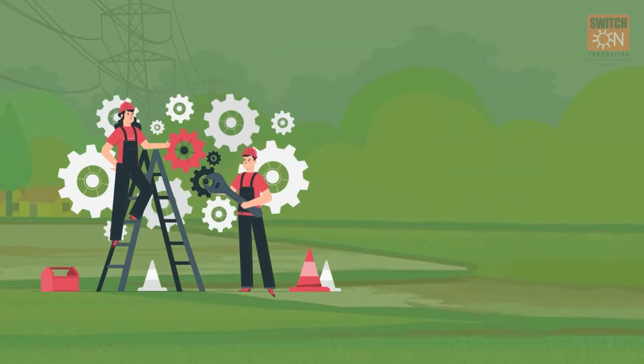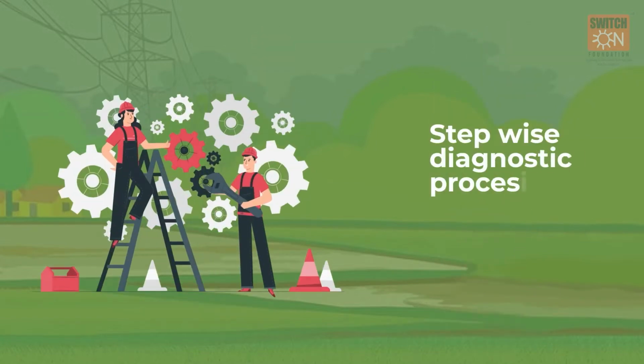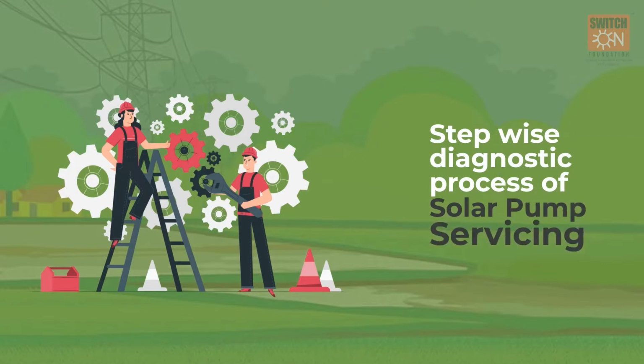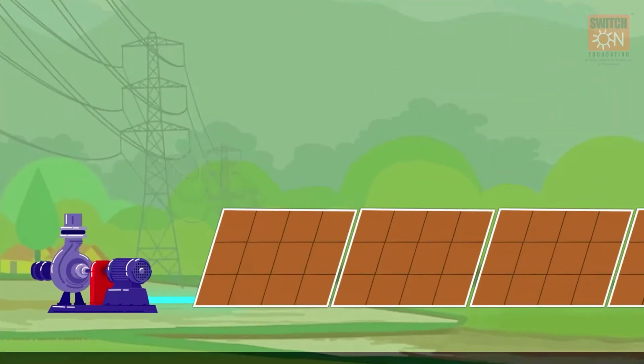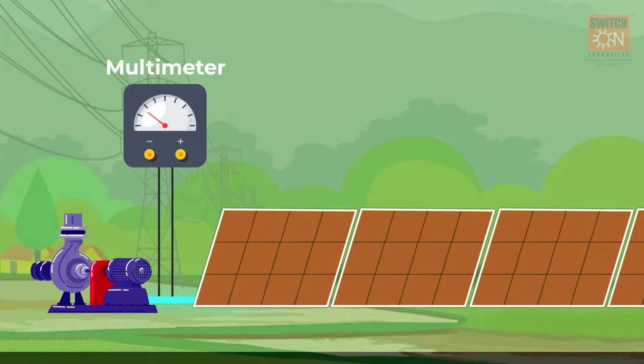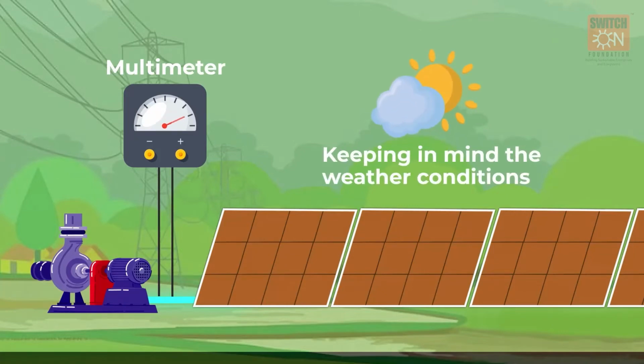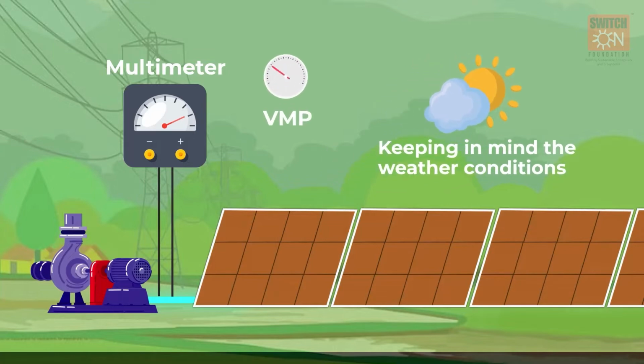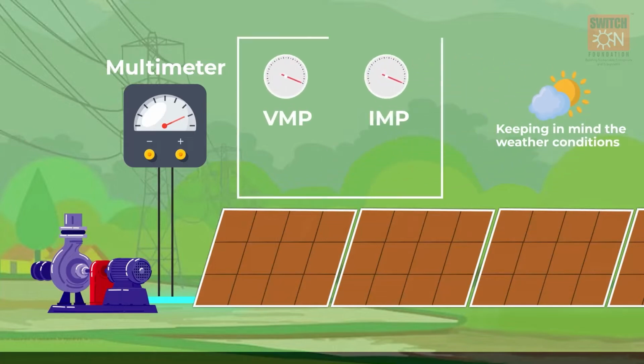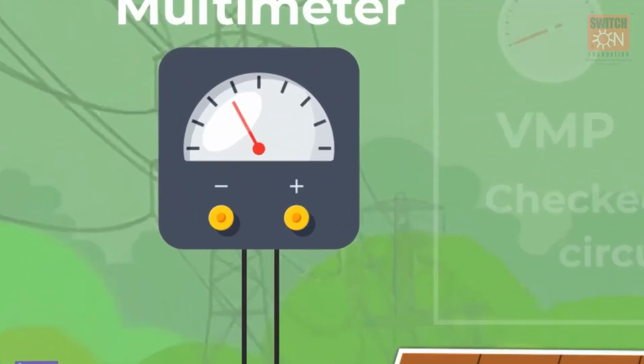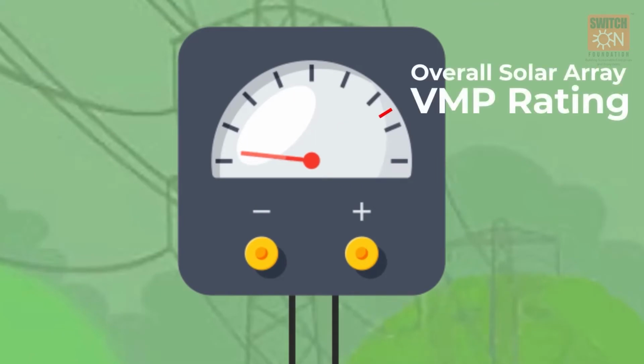Let's discuss the stepwise diagnostic process for a solar pump servicing. In the first step, check the voltage and current of the solar array using a multimeter, keeping in mind the weather conditions. The VMP and IMP should be checked in closed circuit only. If the voltage rating comes below the overall solar array VMP rating, a few things need to be checked.